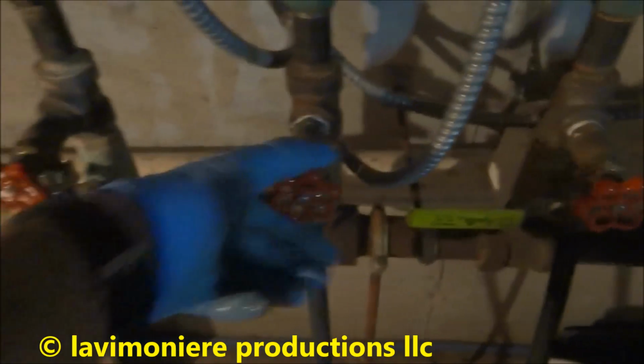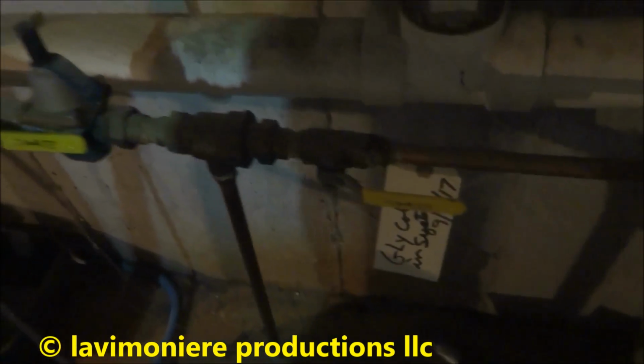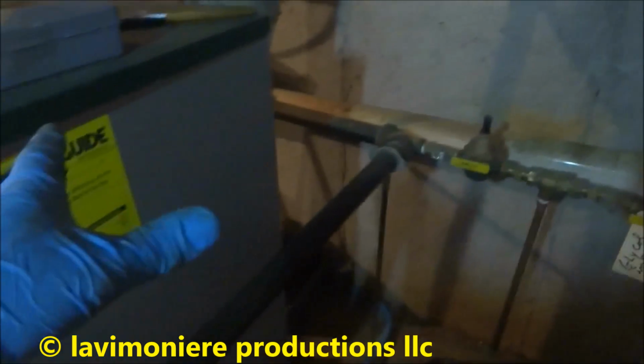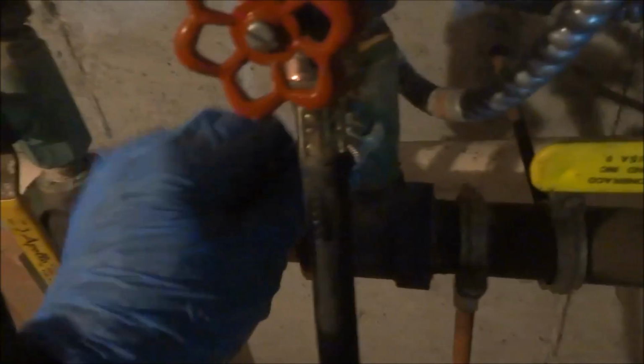So I got these three off, and I got this boiler drain here off. Alright. We're good. Oh, we can restore the water feeder. In case we lose anything, this will fill in. That's it. And I'll pull all my stuff off and then we'll check the antifreeze. All I have to do is open these three. Restore the flow to the boiler.